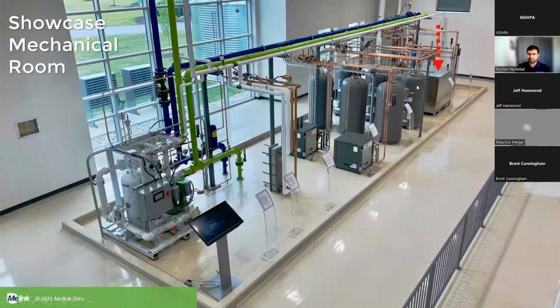We wanted to have some sort of an electric water heating backup because we would produce so much excess electricity. It would be cheaper to heat water to use for building to heat up the building in case some of these other strategies did not work out. What you see far down here are 2 tanks. These are thermal energy storage tanks using phase change material. The beauty of this particular system is that they change phase at 70 degrees Fahrenheit.